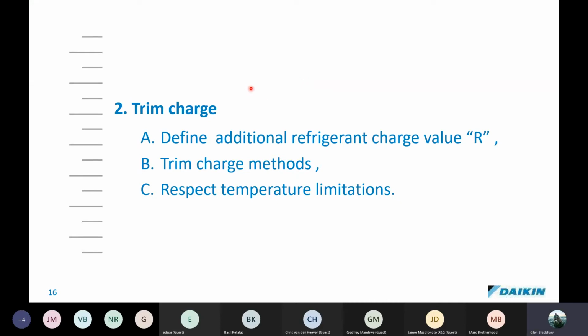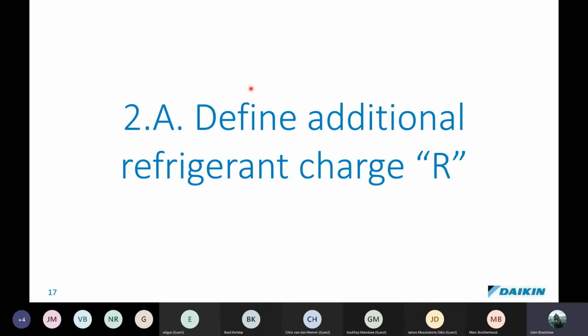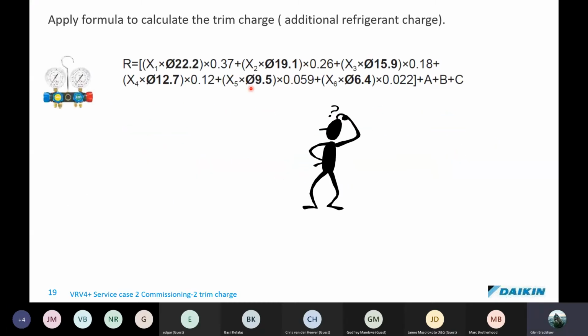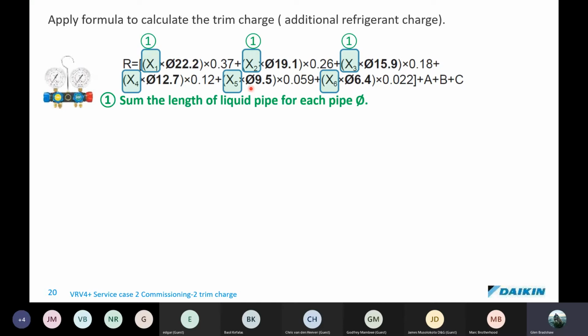The trim charge, okay, well, the additional amount of refrigerant, okay. We're also going to look at trim charge methods, okay, and respect temperature limitations on there. All right, so in calculating, you've probably seen a formula like that somewhere in the installation book when you were reading it, okay, and you wonder what it's about. Well, basically, in order to calculate the refrigerant charge, we need to go through a number of steps to make sure that it is correct.